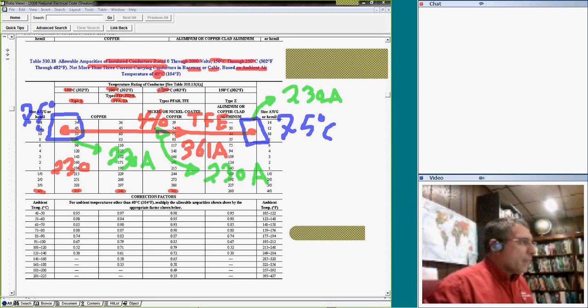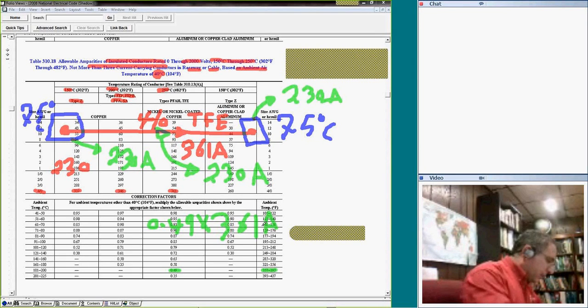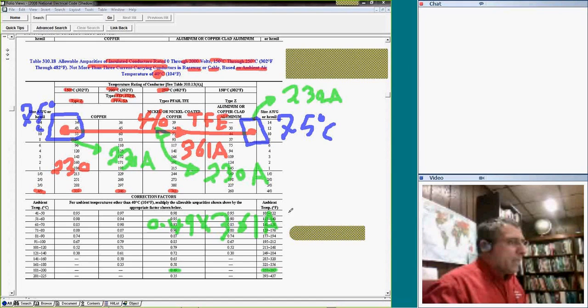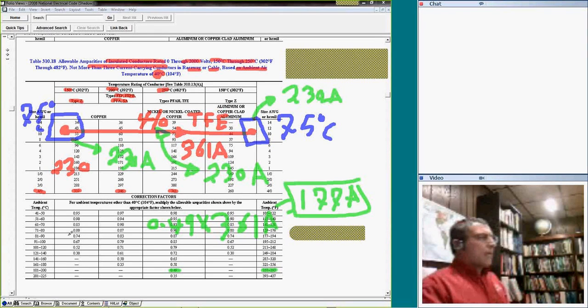Suppose my temperature was this amount. Remember, these are going to be in places where it's extremely hot. Look at the correction factor. Now I can use 0.49 times 361 amps. That will give me 177 amps. So this conductor cannot carry more than 177 amps.